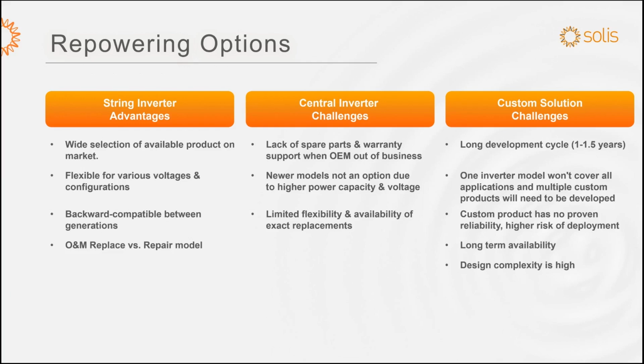Backward compatible between generations. What that means is if you have, for example, a 100 kilowatt inverter from Solis today that you replace in a repowering project, we will be backward compatible in another 5 years with a similar product, maybe with more features, maybe with additional certification, but the product will be similar and backward compatible. And an O&M replace-versus-repair model: there are no trained technicians or service people needed to repair the inverters. You basically replace them with an equivalent inverter, sometimes even from a different manufacturer, because among string inverters there are multiple manufacturers that are backward compatible with each other.